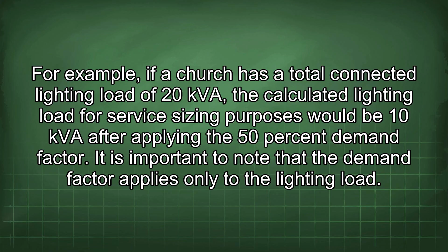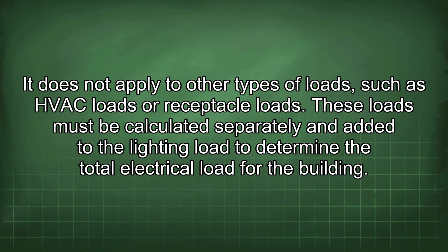It is important to note that the demand factor applies only to the lighting load. It does not apply to other types of loads, such as HVAC loads or receptacle loads. These loads must be calculated separately and added to the lighting load to determine the total electrical load for the building. In addition to the NEC requirements, local building codes may have additional requirements or restrictions regarding the application of demand factors. It is crucial to consult with the local building inspector or qualified electrician to ensure compliance with all applicable codes and regulations. The building inspector may require documentation or calculations to support the application of the diversity factor.